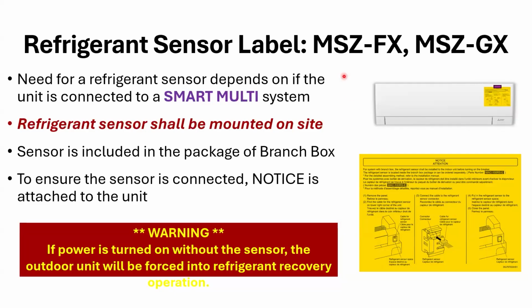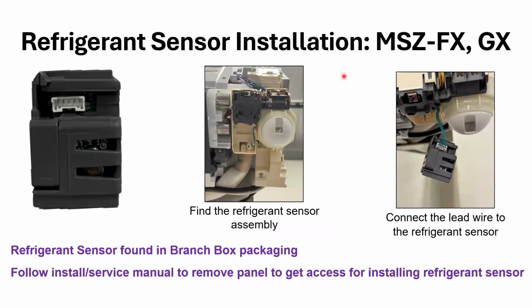So they're trying, right, to notify you everything they can about the refrigerant sensor, here's how to install it, etc. So here's how to install the sensor on these particular units. This is what the sensor looks like, found in the branch box packaging. Follow the install service manual to remove the panel and get access for installing the refrigerant sensor. So here is the area where the sensor goes.